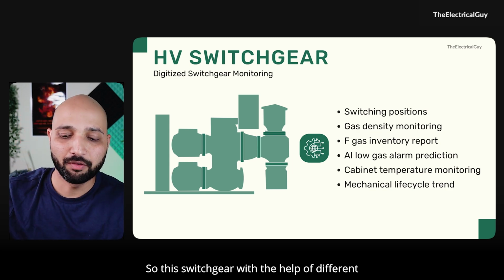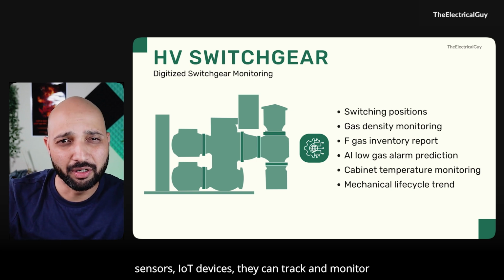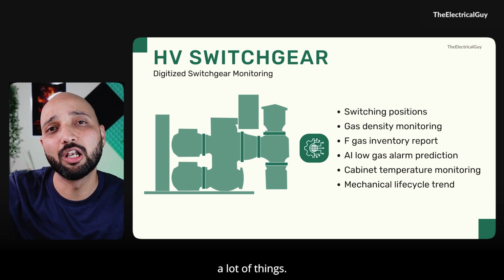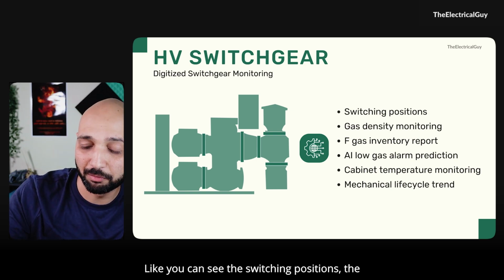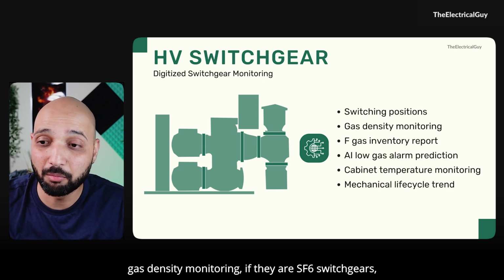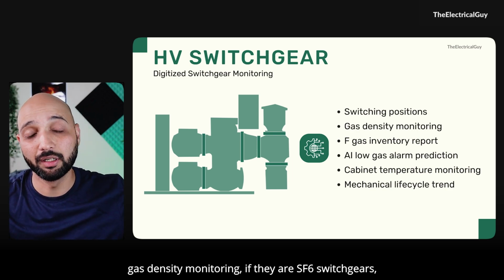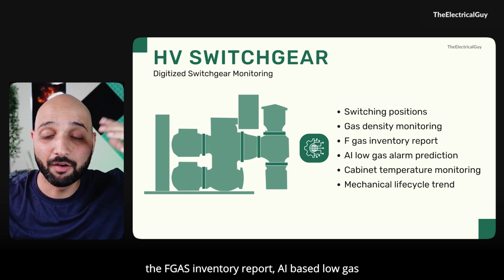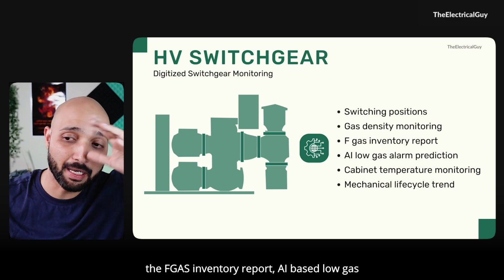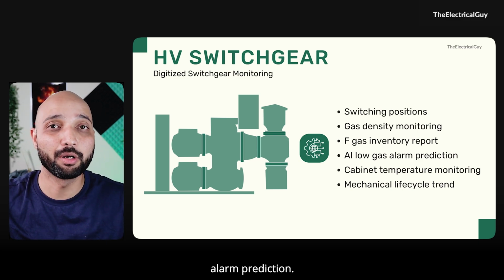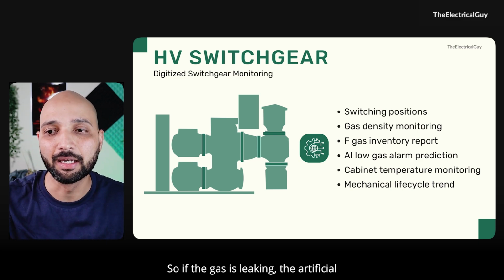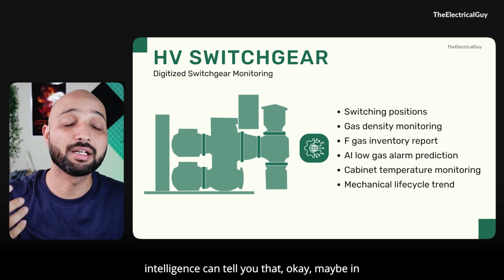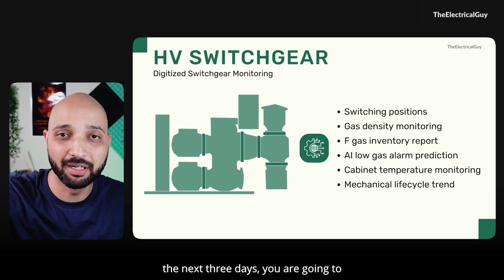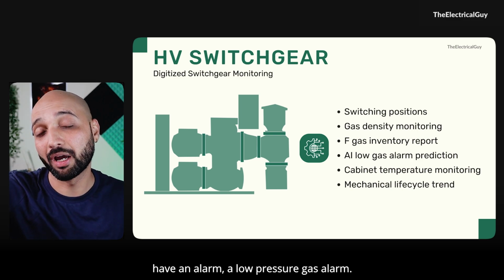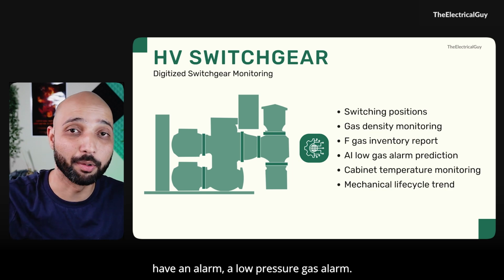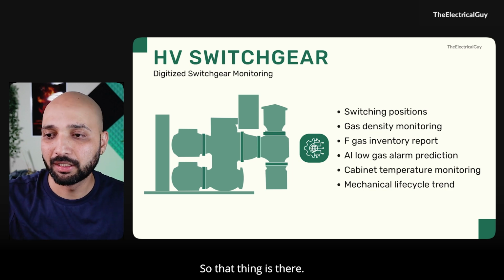With the help of different sensors and IoT devices, the switchgear can track and monitor a lot of things, like switching positions, gas density monitoring for SF6 switchgears, F-gas inventory reports, and AI-based low gas alarm prediction. If the gas is leaking, the AI can tell you that maybe in the next 3 days you're going to have a low pressure gas alarm.